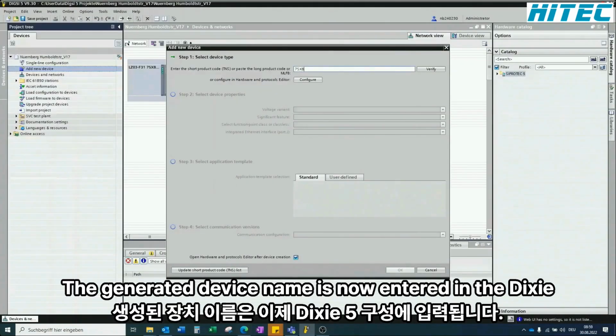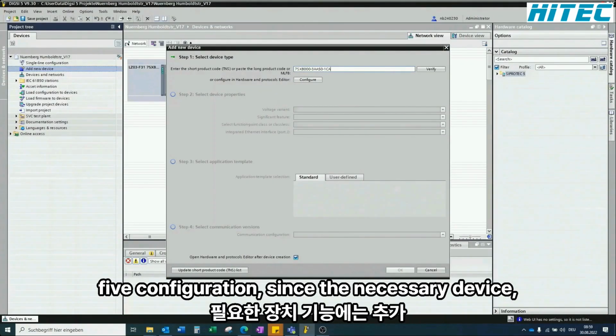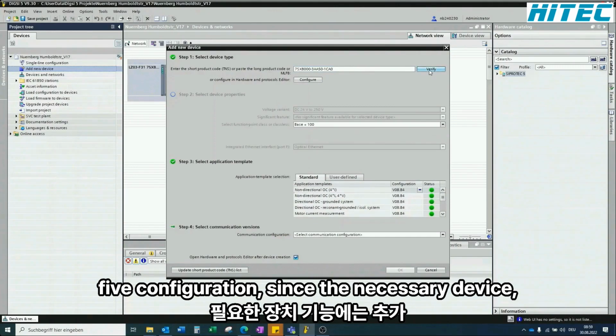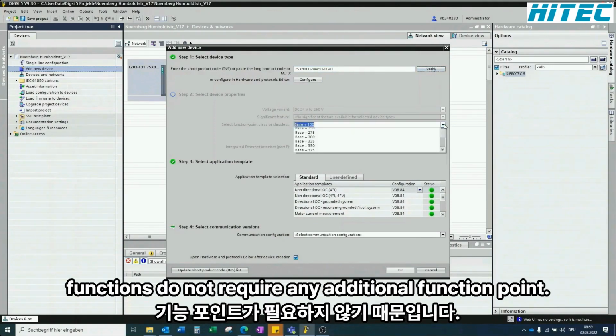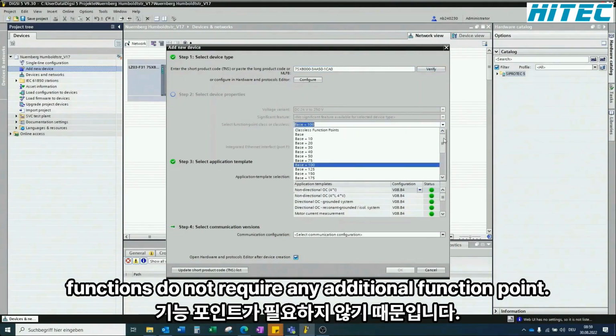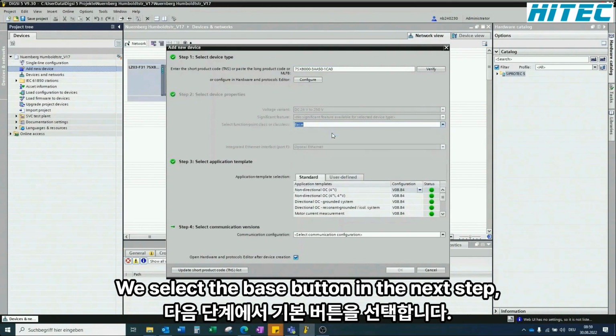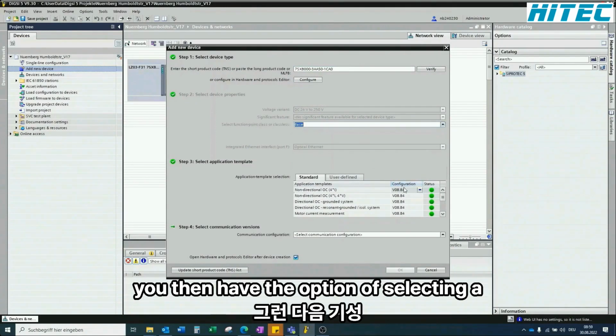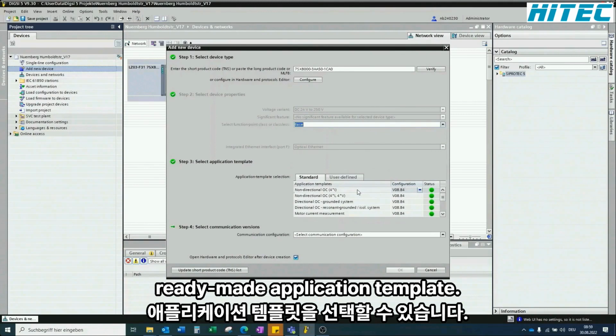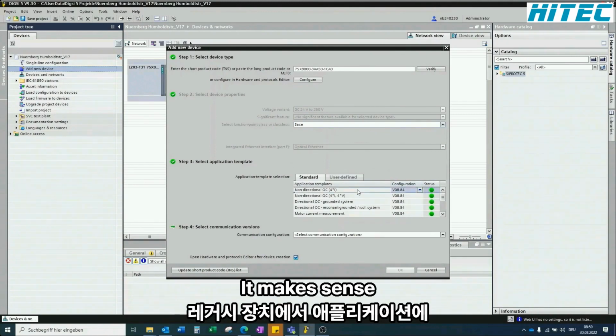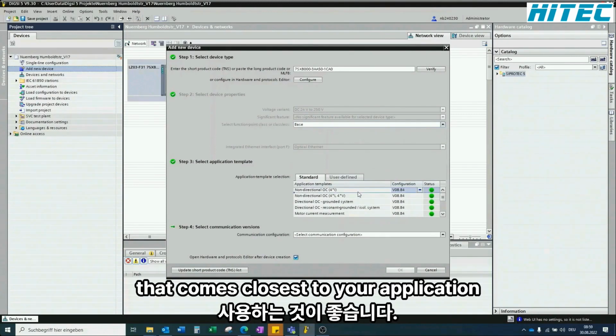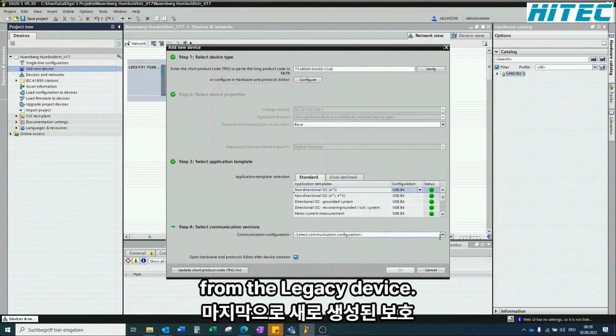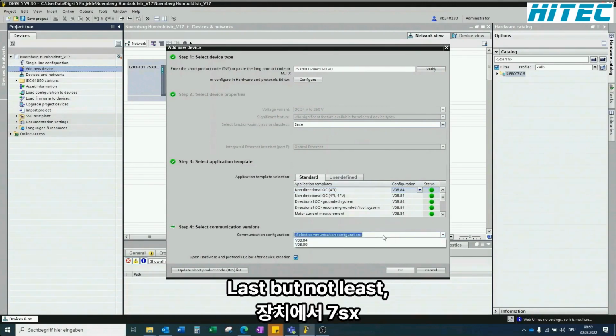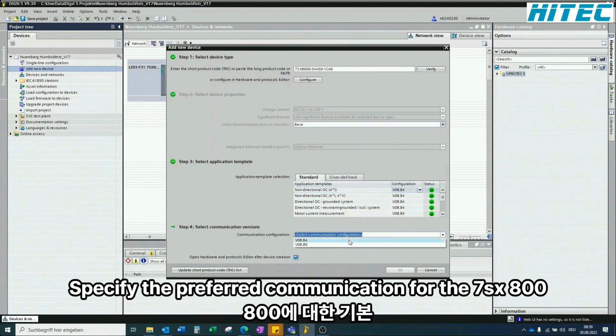The generated device name is now entered in the DIGSI 5 configuration. Since the necessary device functions do not require any additional function points, we select the base button in the next step. You then have the option of selecting a ready-made application template. It makes sense to use the template that comes closest to your application from the legacy device. Last but not least, specify the preferred communication for the 7SX800.